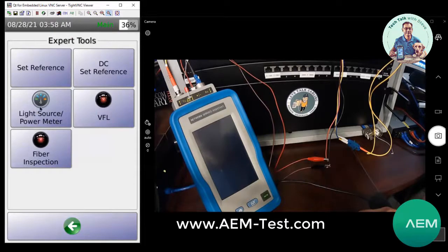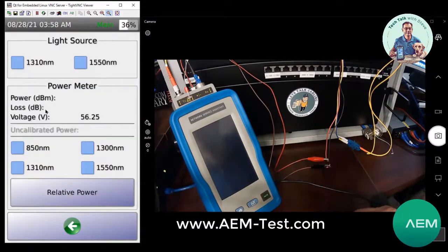You've also got standalone light source and power meter mode. In this mode, we can measure the absolute power coming from the far end, and see the voltage if it's hooked up, at both 1310 and 1550. This can be set up as just a light source or just a power meter. So if you have a secondary light source on the far end, or just want to measure the absolute power coming from the equipment, you can do that as well.